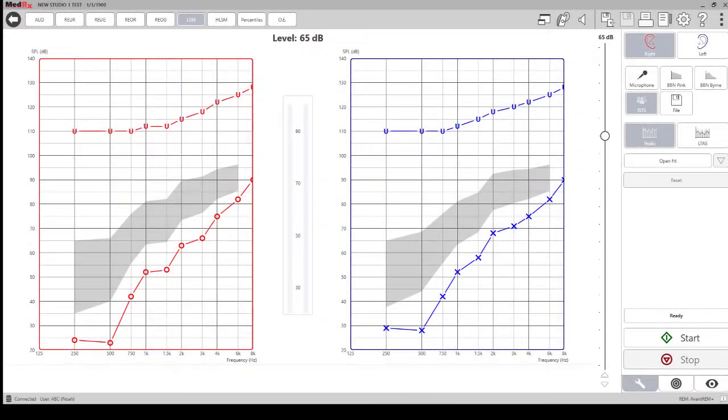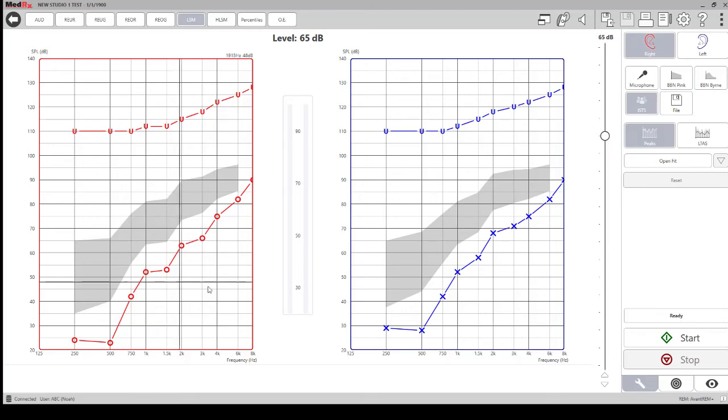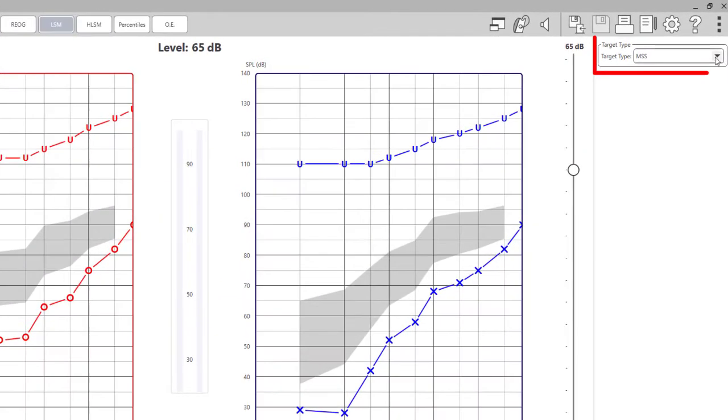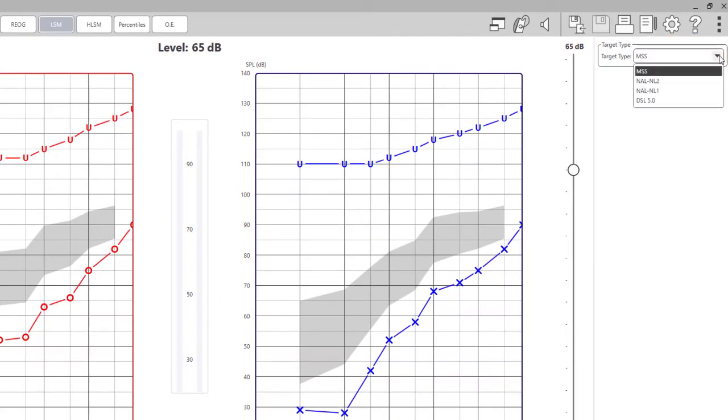On the right hand side of the screen you can change the characteristics of the test and the target types. You can click on the target tab at the bottom and this is where you can change your target type from either MSS or another fitting formula such as NAL2.